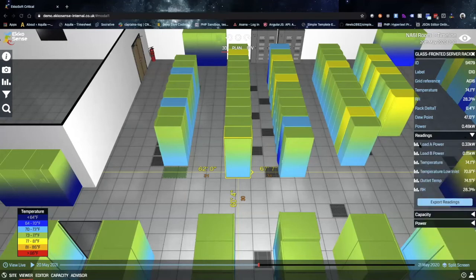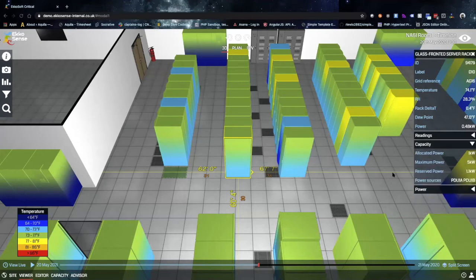Then we can expand into the readings some more. So load A and B power draws, the temperature, which is the top inlet temperature, the low inlet temperature, the outlet temperature, as well as the relative humidity. Then we can see some capacity information, so allocated power, the maximum power that this rack can handle, the reserved power, as well as the power sources that this rack is drawing from. And then we can just see some general power information, so the power type, so if it's DC, UPS, Fed, we'll see that here, and then the different load A and B powers.